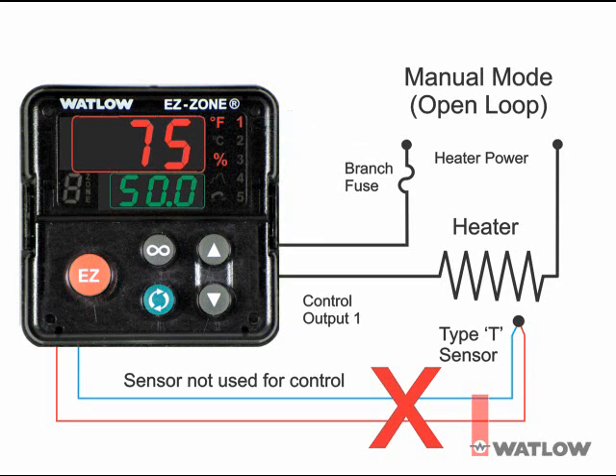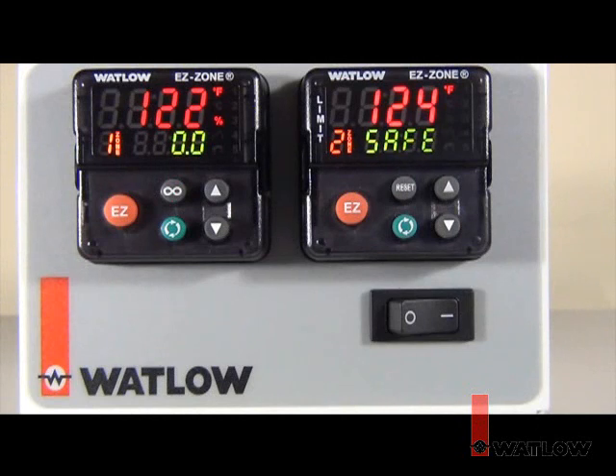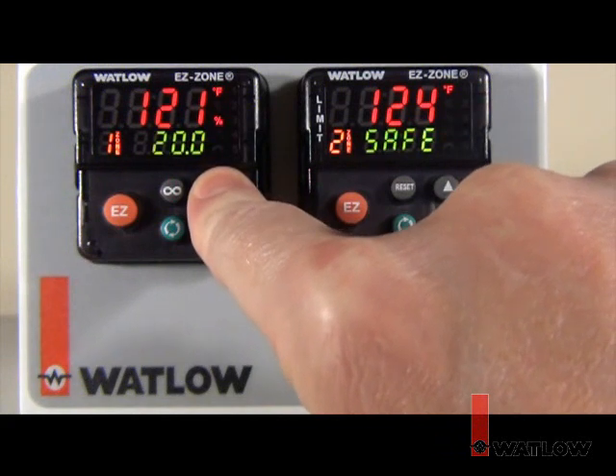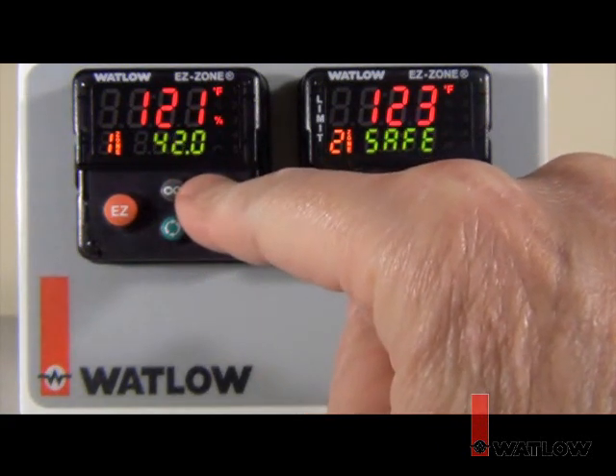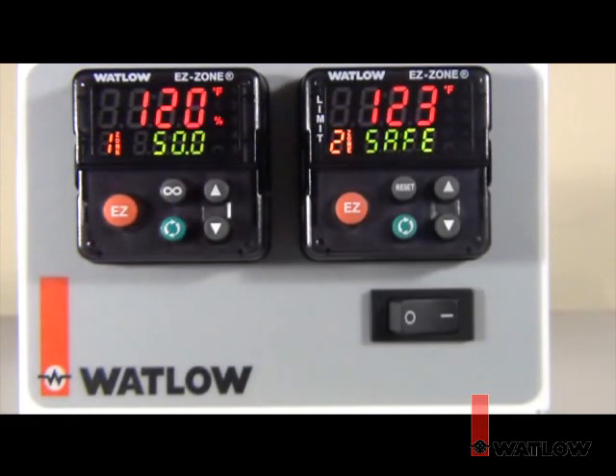Note that 0.1 to 100.0% settings represent heating, and negative 0.1 to negative 100.0% represent a cooling request for power. An open loop setpoint set at 50% causes the heater to produce 50% of available power. The output indicator will flash at a 50% rate to indicate this setting. The process will stabilize at a temperature where 50% heat applied to the load equals the heat lost by the system.